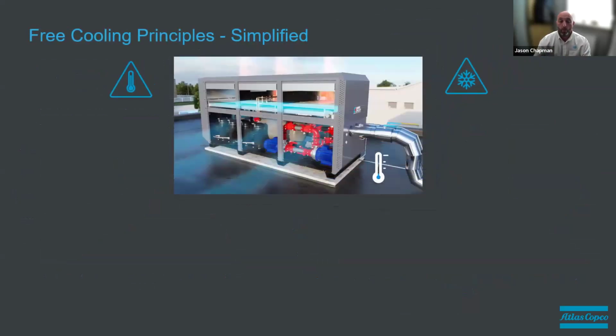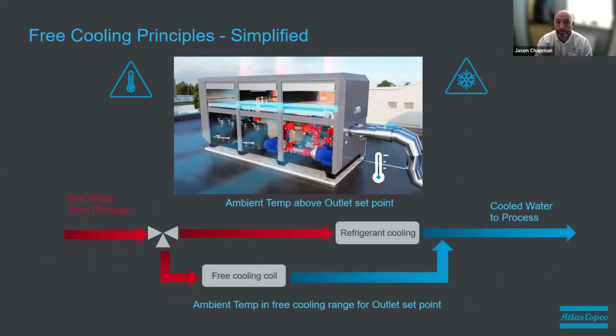what we can see there is the hot water from your process comes back to the chiller, the cooler. It goes through a three-way valve, depending on the ambient temperature. It will either divert it through the free cooling coil, which is highlighted in blue in the picture at the top. It'll either then go back into the circuit, or the motorized valve will divert it straight into the refrigerant cooling, depending on the ambient temperature. What is omitted from here, which I put on there, is partial free cooling. It's where it can divert so much of the process through the free cooling, the rest through the refrigerants. It's just getting the best of the system without running flat out on one or the other.